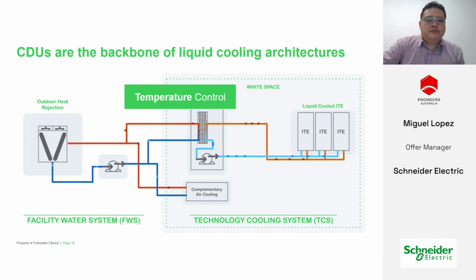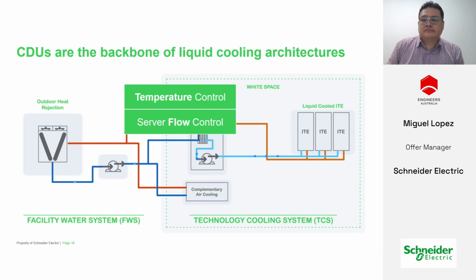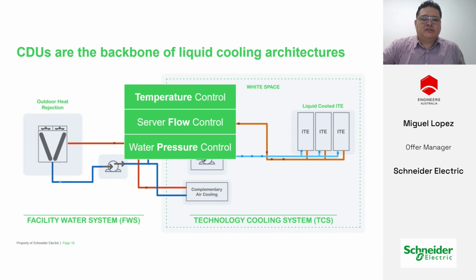So the purpose of the CDU, in a nutshell, is to control the temperature to and from the AI-ready servers, to control and accurately deliver the water flow to the servers. Now, your server manufacturer, Dell, HP, and others, will nominate what their range of temperature of the medium, the water coming into their cold plate, should be and what the flow rate should be. So the CDU must be configured to be able to deliver those within those parameters. Water pressure, as you can imagine, recirculating water through a pump. Those with a mechanical background will understand there's a pressure loss as a result of running water through very small apertures which are leading back to the cold plate. So the pump fitted in the CDU must be capable of overcoming all the pressure losses of each individual server, of each individual cold plate.